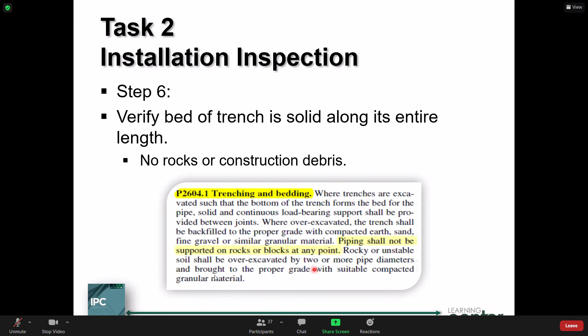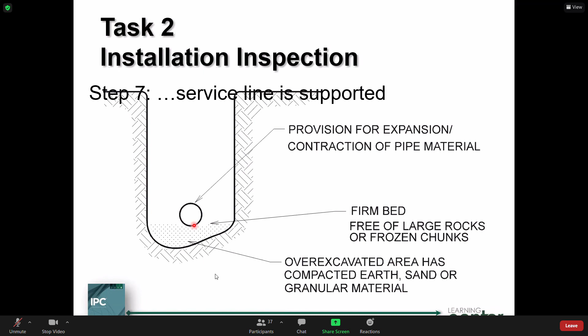2604.1. Hey, piping shall not be supported on rocks or blocks at any point. What are we talking about? We're talking about bedding the pipe. Take a look at this here. We want a nice firm bed along the total longitudinal length of the pipe. We want to support it along its length in the trench. In other words, we don't want to put a rock here or a brick to support the pipe every 10 feet. What would that do for us if we supported the pipe every 10 feet on a couple of boulders or rocks?